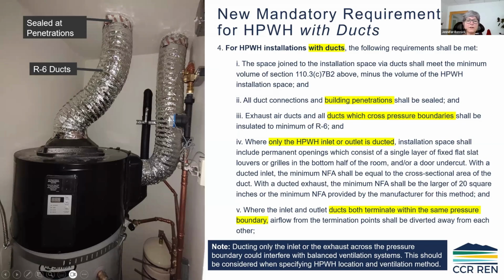In certain climates it makes sense to duct it to the outdoors. This is an example of a project in climate zone 5 or climate zone 3, where it's mild enough that they were able to duct the unit's inlet and outlet. You could also do it in your attic or outdoors. It breaks the pressure boundary, so you seal penetrations and use an R6 duct, but it was done because the homeowner didn't want cool air blowing into the hallway where the unit was located.